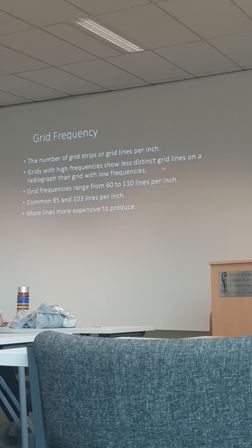Those with high frequencies show less distinct grid lines on a radiograph than those with low frequencies. Obviously, more lines means more lead, and it's more expensive to produce.